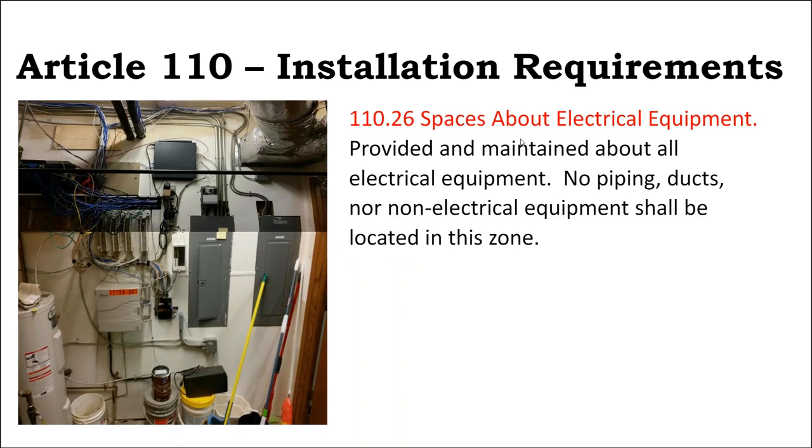So here is an electrical control room, and it's a little messy, I'll give you that. The question is, is there an electric code violation in this room? One kind of hard rule is that electrical space needs to be dedicated. You can't have gas lines running through your electrical space. You can't have plumbing lines. You can't even have HVAC lines running through your electrical space. You can have electrical stuff running through your electrical space, but you can't have other scope running through your electrical space.